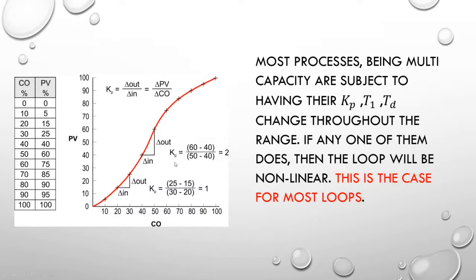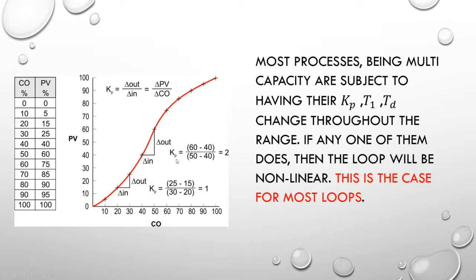Most processes culminate with the characteristics of an integrating, first order, and dead time process, which leads them to be largely multi-capacity processes. As such, they are subject to having the KP, T1 time, and dead time change throughout the range. If any one of these does, then the loop will be non-linear. As I move this triangle up and down the line, I get different gain values. This is important because we have to select a gain value that works well in the operating range we intend to run in. It will run best there, but differently in other operating ranges.